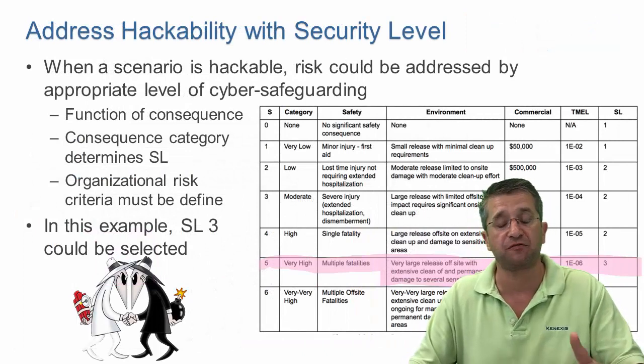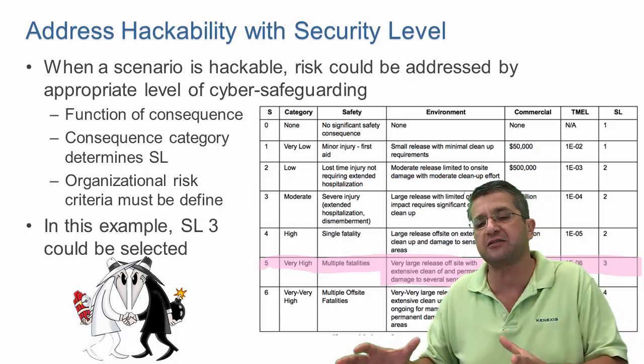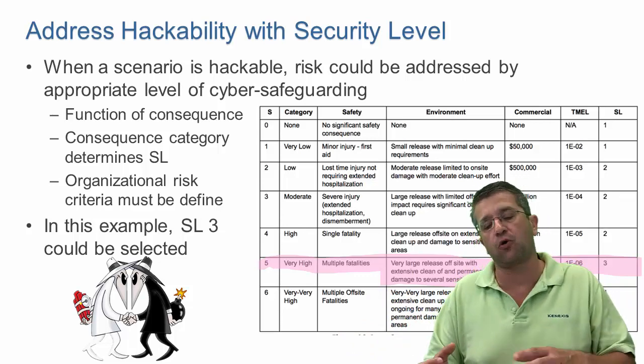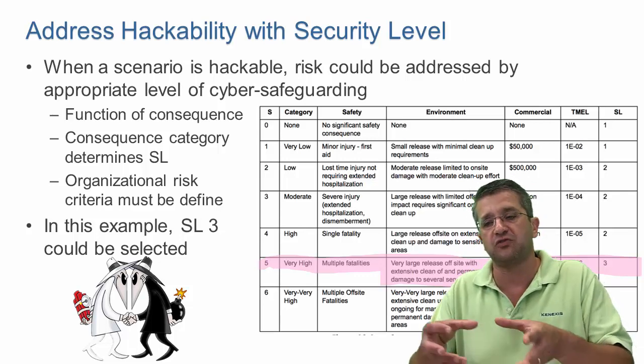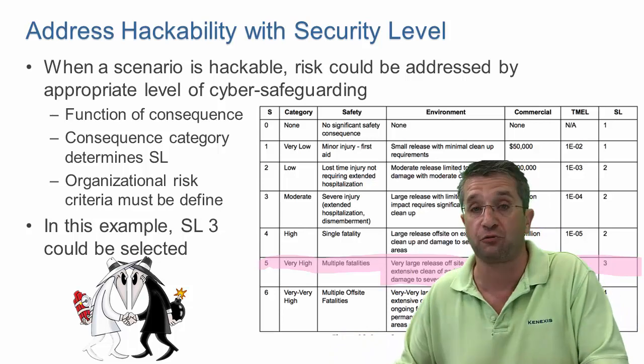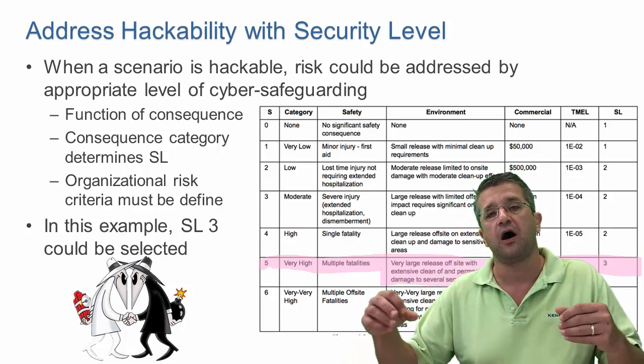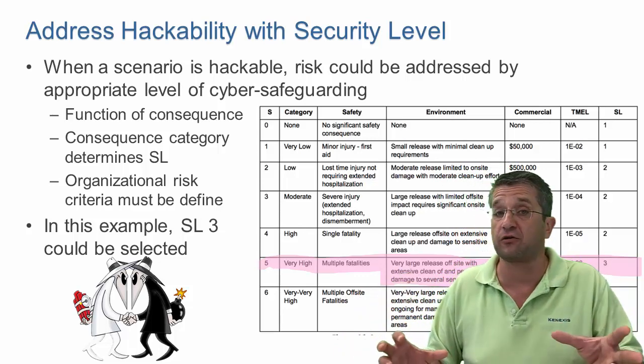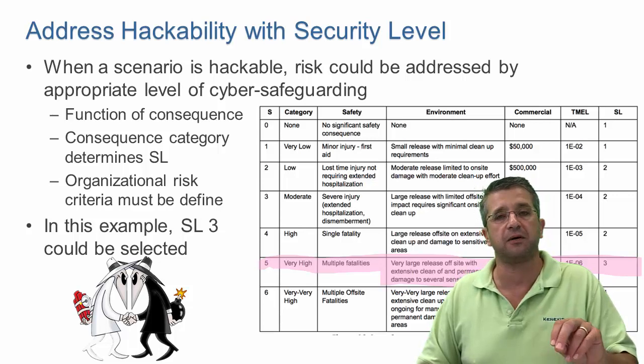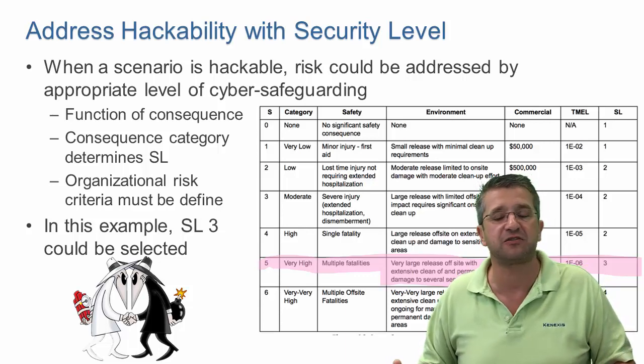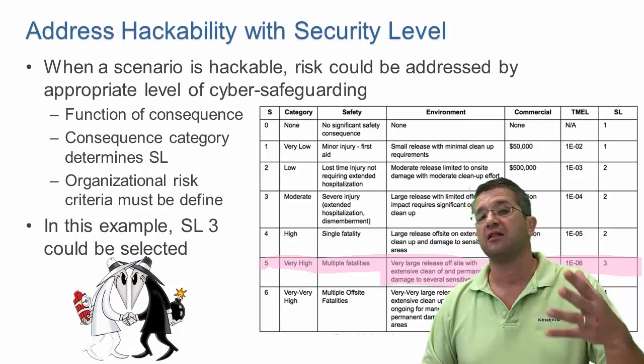We can do two things. First, we can look at the scenario and say the consequence is bad and it's hackable, so we need to assign an appropriate security level. A very high consequence could result in a security level of 3 under IEC 62443, which is a very high requirement for cyber hygiene and safeguarding — difficult to achieve and requires a lot of work. But from the process engineering and functional safety perspective, let's also look at preventing this without using cybersecurity.